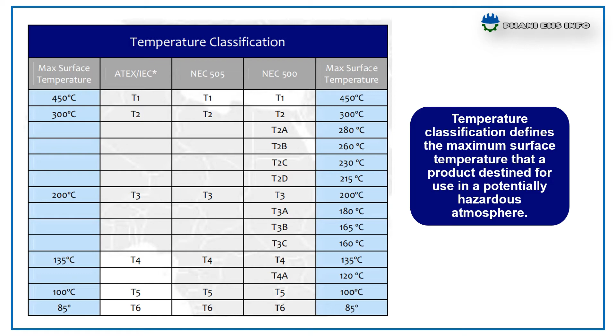The temperature is classified into 6 categories based on the ignition temperature of gas or vapor. They are T1, T2, T3, T4, T5, T6. Accordingly, the maximum surface temperatures are 450, 300, 200, 135, 100, 85 as shown in this table. For example, a product with the T code of T3 means the maximum surface temperature will not exceed 200 degrees Celsius.